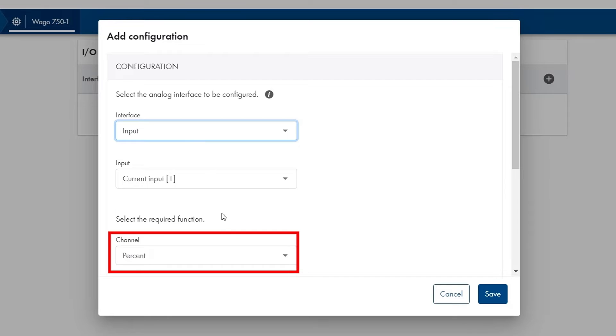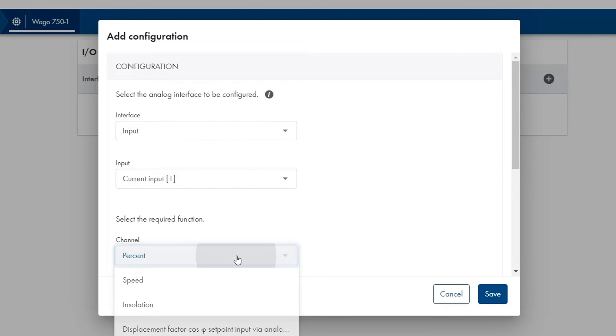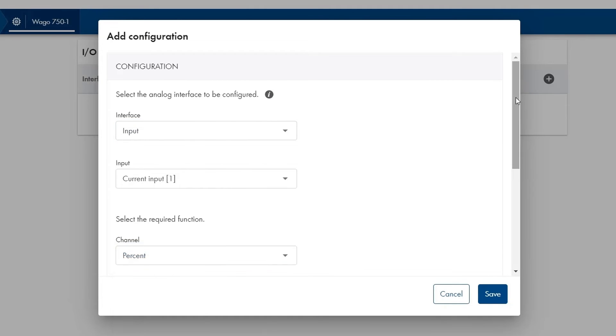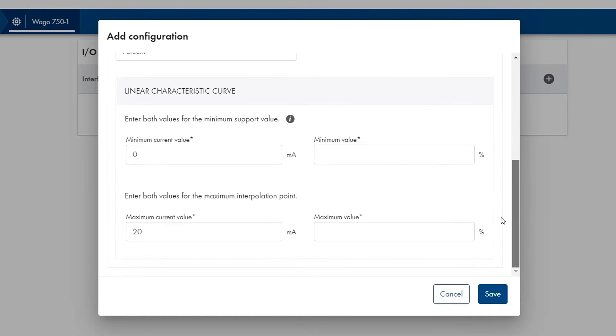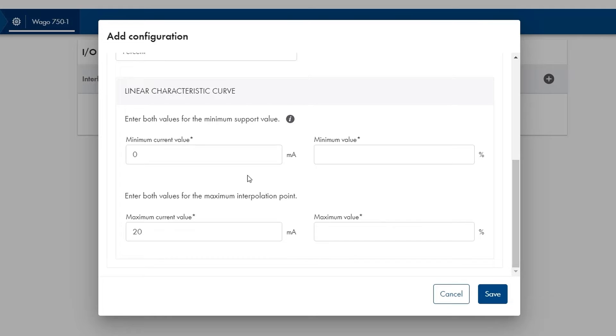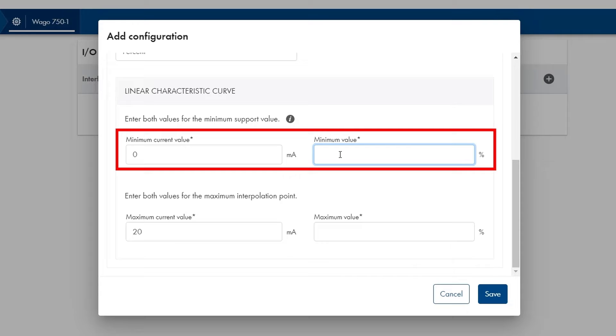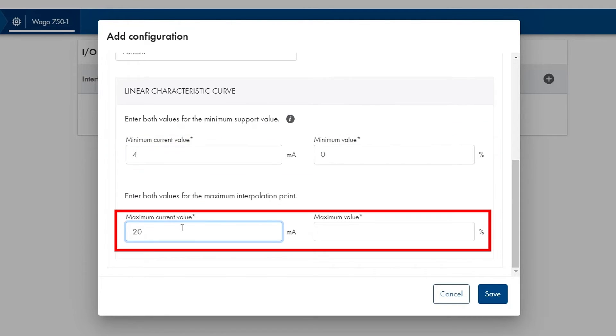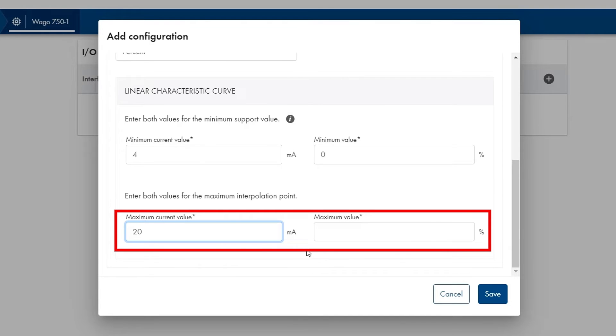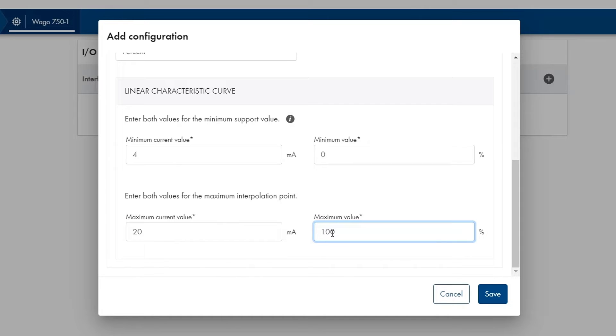Then percent since I would like to see the fill status in percent. In my case the linear characteristic curve has 4 milliamps as minimum current value which corresponds to 0 percent or tank empty. The 20 milliamps is the maximum current value and this corresponds to 100 percent or tank full.